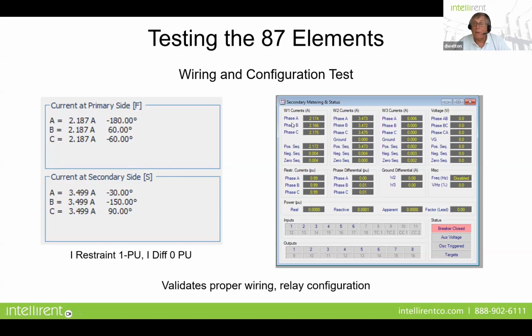Basically, what you see here in the metering screen, and this comes from the Beckwith relay, and you see the same thing with the metering values from Schweitzer, is that I've got my winding 1 currents, my winding 2 currents, and what I'm looking for to make sure everything's wired properly is all positive sequence currents on both the primary and the secondary winding. And you'll notice that I apply these values, I'm not tripping the relay, I don't get any outputs activated. Well, that's good, because that's what you want to have happen. This is just a simple basic wiring check, the sanity check, I call it, to make sure that everything's wired properly.